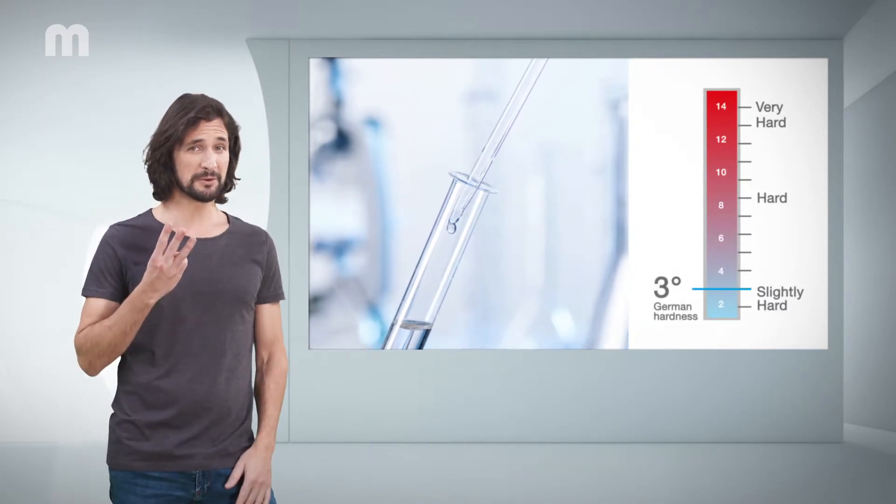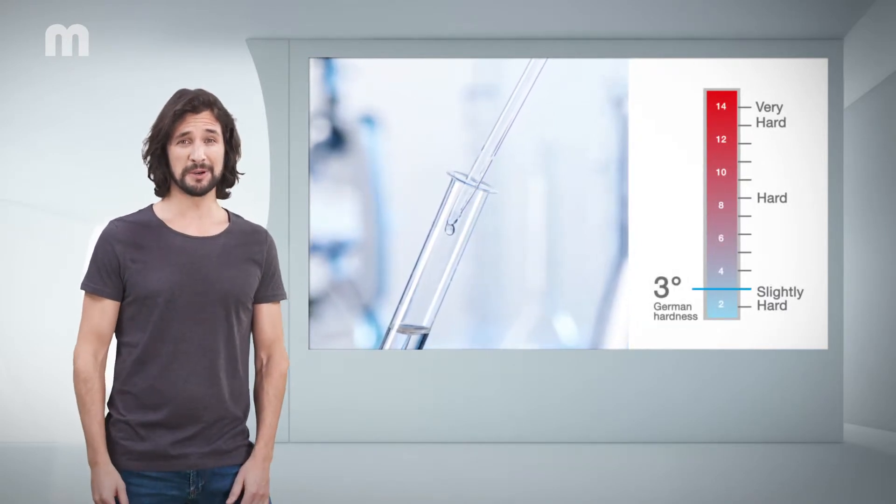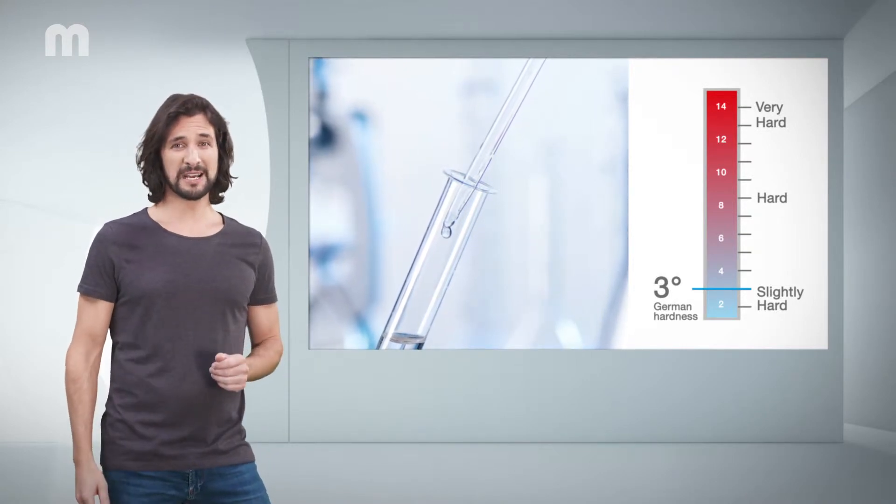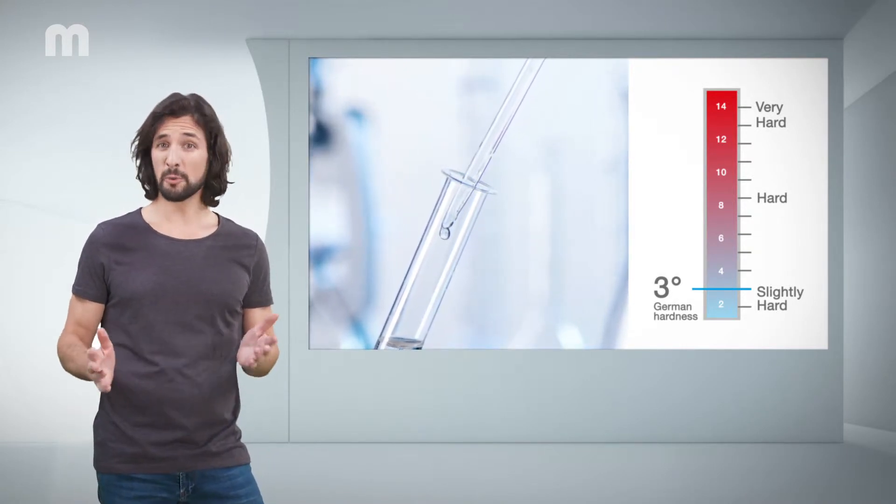In professional dishwashing, a maximum water hardness of 3 degrees generally applies for feed water. What comes out is crucial for deciding on what is the best solution for your water treatment.